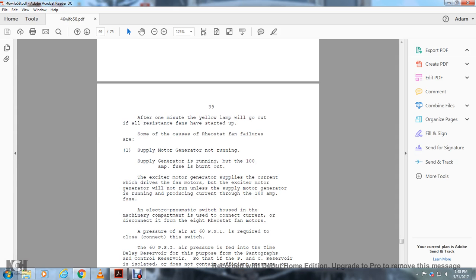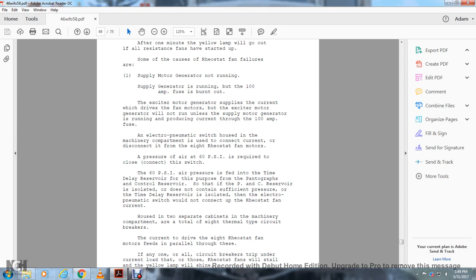Some of the causes of the rheostat fan failures are: Supply Motor Generator not running. Supply Generator is running, but the 100 amp fuse is burnt out. The exciter motor generator is supplied with the current which drives the fan motor. The exciter motor generator will not run unless the supply motor generator is running, producing current through the 100 amp fuse.